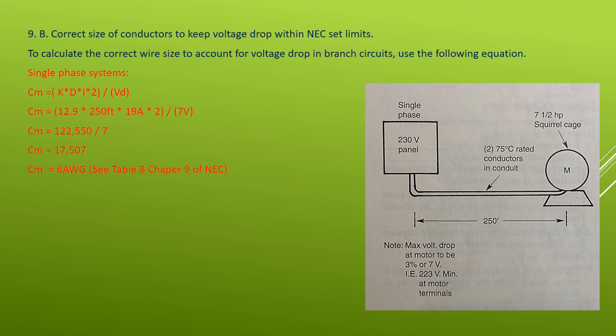If we look at the circular mil value at Table 8, Chapter 9 of the NEC, we find that it is in between AWG 8 and AWG 6, and we always go with the larger size, 6 AWG.